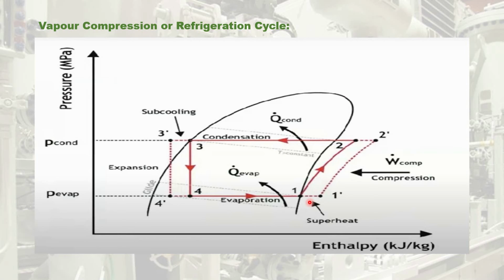Here in this graph, you can observe that the process 1 to 2, compression, is doing work for compressing the gaseous refrigerant received from the evaporator. After compressing the gaseous refrigerant, it is increasing the saturation temperature and the saturation pressure. Now, the raised saturation temperature must be cooled down in the condenser. So now, the condenser's work is to cool the raised saturation temperature of the gaseous refrigerant and change its phase from vapor to liquid. And this is where the process is started by the condenser.